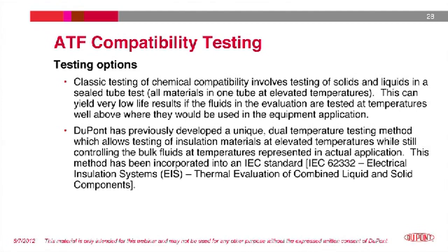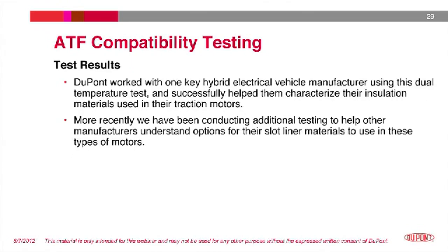This can yield very low life results if the fluids in the evaluation are tested at temperatures well above where they would be used in the equipment application. DuPont has previously developed a unique dual temperature testing method which allows testing of insulation materials at elevated temperatures while still controlling the bulk fluids at temperatures represented in the actual application. This method has been incorporated into an IEC standard, IEC 62332, Electrical Insulation Systems, Thermal Evaluation of Combined Liquid and Solid Components. DuPont worked with one key hybrid electric vehicle manufacturer using this dual temperature test and successfully helped them characterize their insulation materials used in their traction motors.